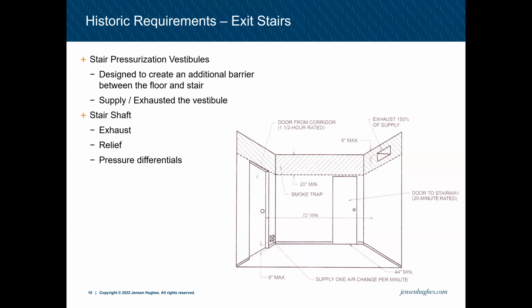Additional historical requirements include stair exhaust. There used to be requirements in the third and fourth editions of 780 CMR. So buildings 40, 50 plus years old allowed an exhaust relief vent at the top of our stair shaft, trying to accomplish basically the same thing, to keep smoke outside of our stair. However, it was proven to not be as effective as pressurizing the stair.